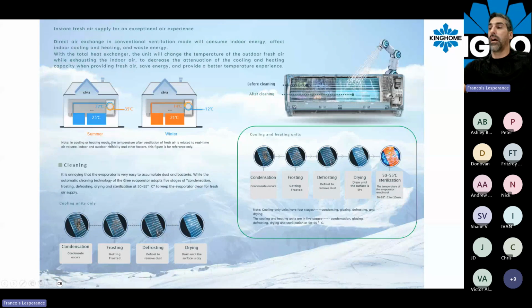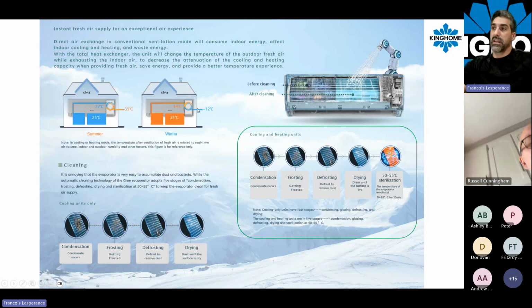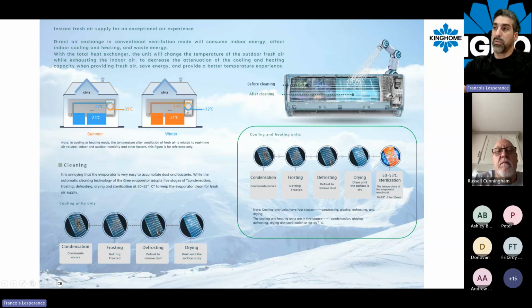So for example, here in winter time, if you take a minus 12 degrees Celsius temperature, we pass it through the heat recovery core. And because it's 21 in the house, for example, we mix the temperature, but not the air. The air goes directly outside and directly inside, but inside that cube, we exchange temperature. So the supply air will be at 14 degrees Celsius. And the system will also know that and will perform as it is supposed to, to keep the temperature at 21 in the house. So we bring in better, fresh air in the room and also maintain a good temperature.